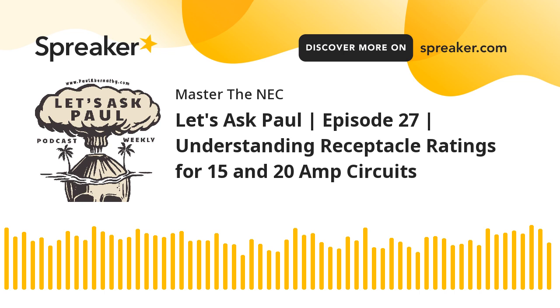Okay, all right. Next, what about a 20 amp rated circuit breaker and a 15 amp simplex receptacle? The answer is no. See how it's opposite here? Previously on a 20, you could have put a 15 amp duplex, but when you're dealing with a single receptacle, a simplex receptacle, you cannot use a 15 amp. Why? Because under the rules for the individual branch circuit, the device has to be equal to or greater than the branch circuit. Well, that 15 is not equal to or greater than the 20 amp overcurrent device, so that would be a violation based on how it's written in 210.21(B)(1).